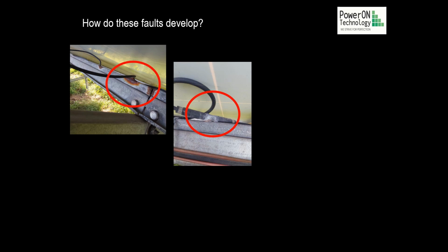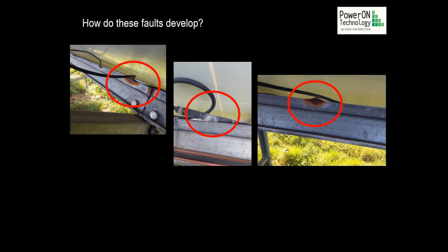Also, inverters can offer no protection against upstream faults which are at the input to the inverter. In fact, as shown in another video, inverters contribute to the fault current. Protection against this type of fault requires a rethink of the DC system protection, and requires new types of protection devices, other than just fuses. The unique current voltage relationship of PV panels makes it difficult to detect a short circuit and protect against it, as is also illustrated in a separate video.